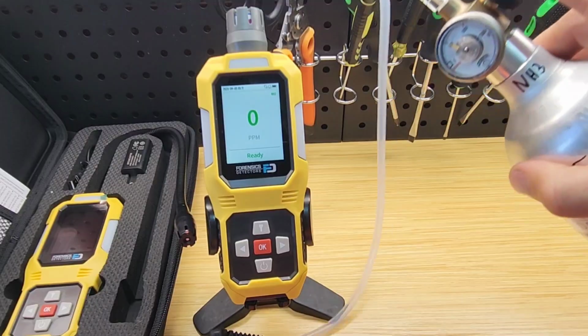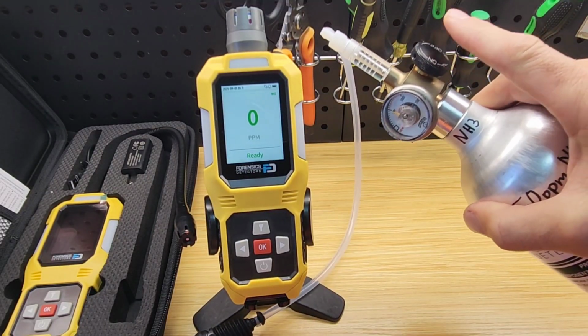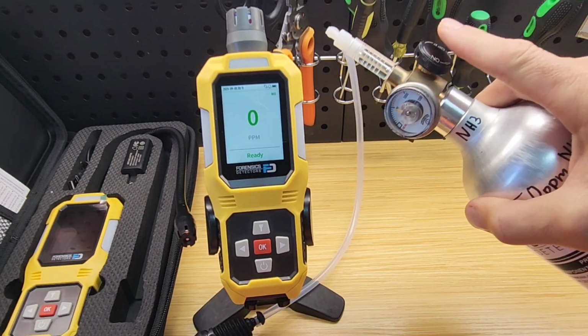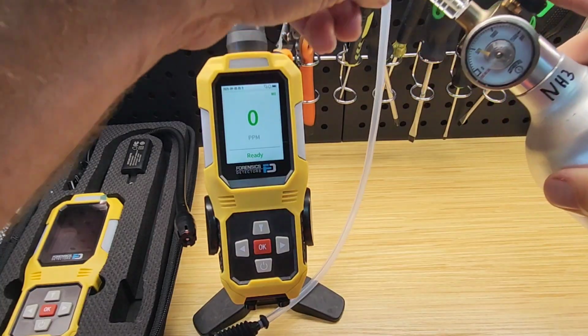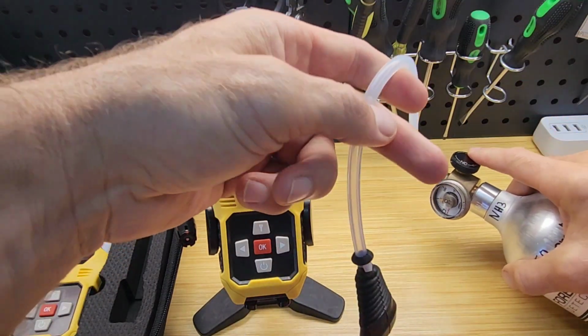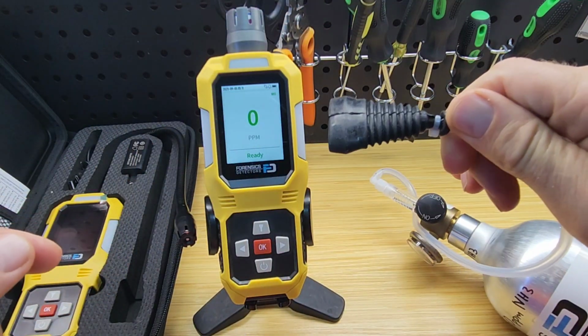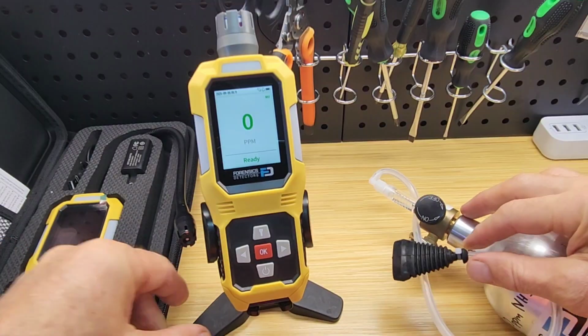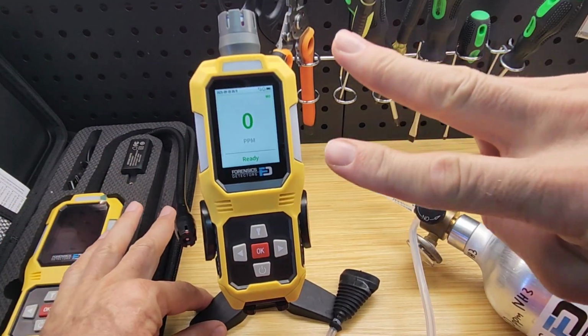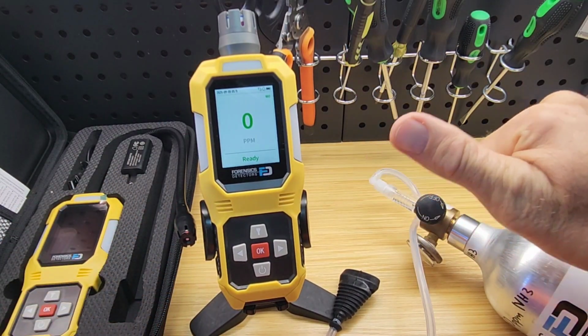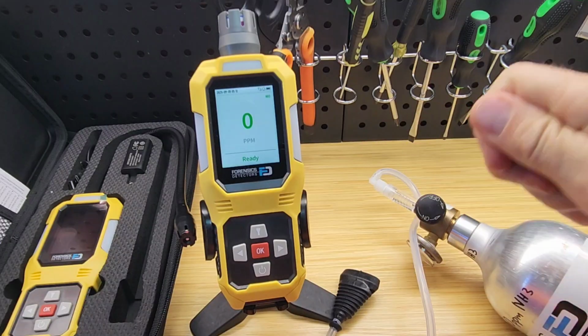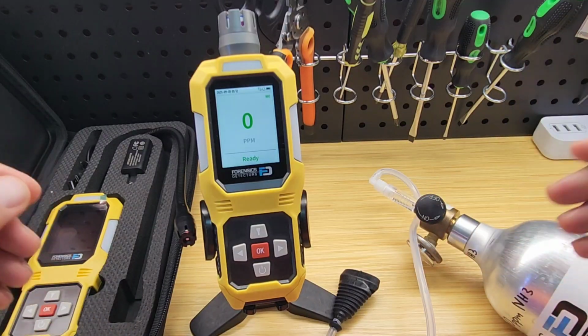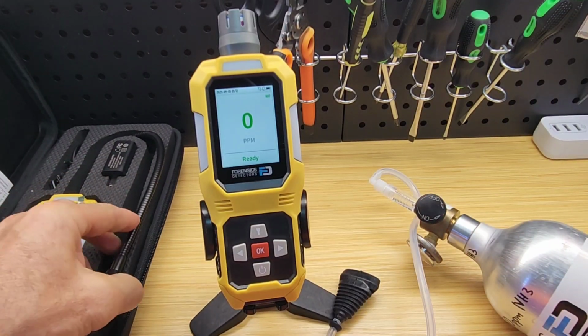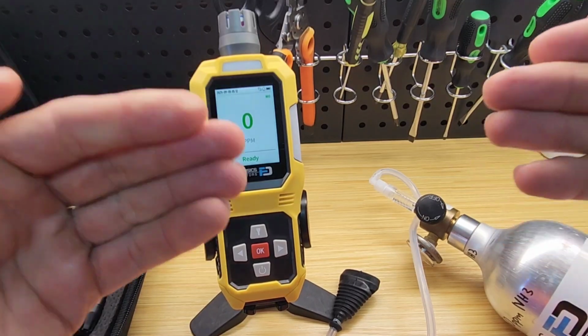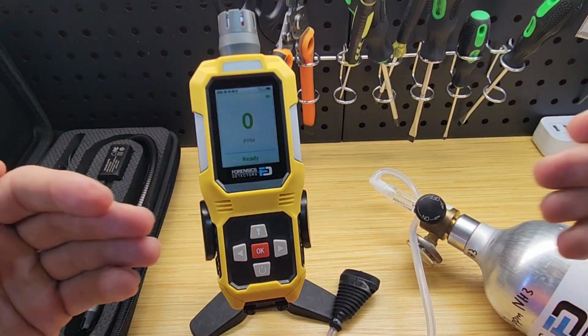Attached to it is our variable low cost, very affordable gas regulator, and attached to that is our FD-92 calibration rubber cap. Now, when it comes to calibration, there's always two main steps. The first is a zero calibration, and then it is a span calibration. So let's begin with step number one. That is a fresh air zero calibration.